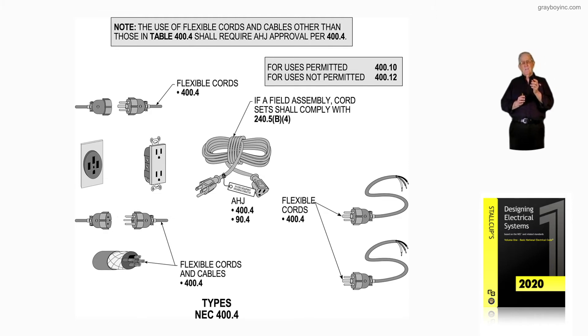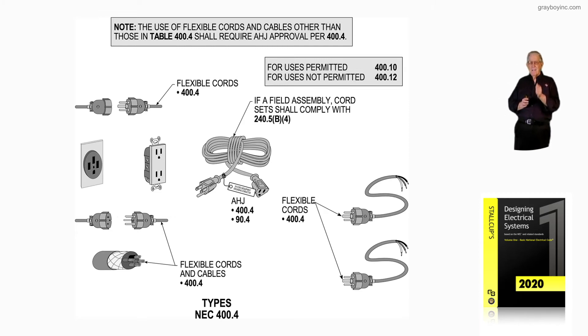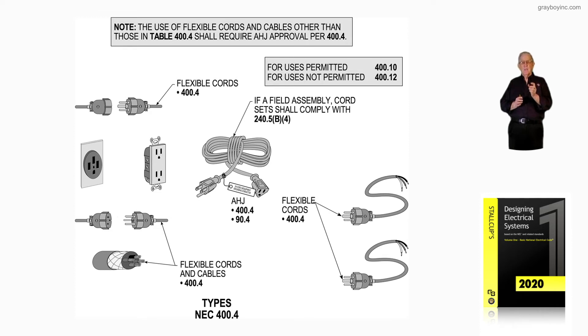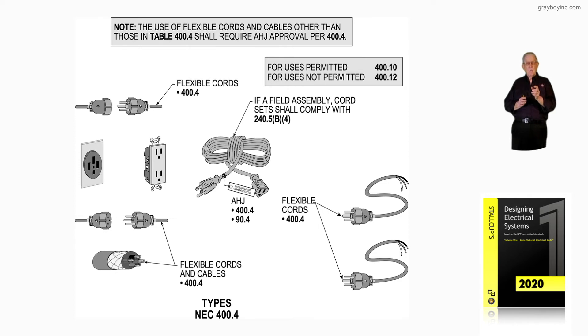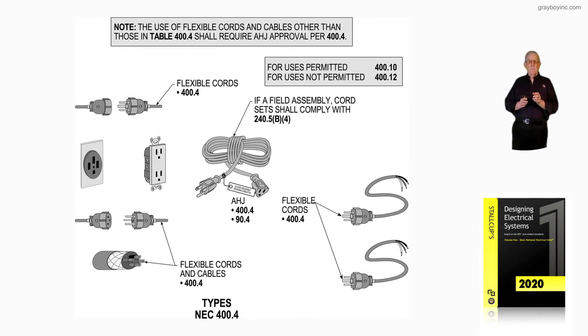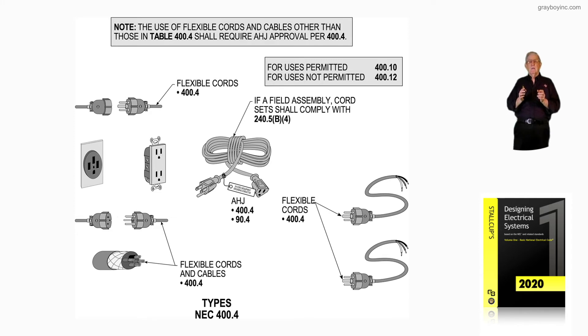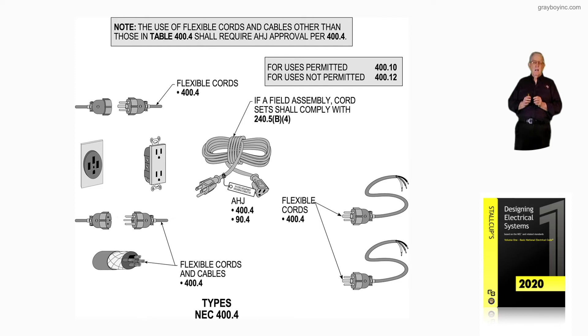And the note says yes, if the type of cable or cord you're using is not in NEC 400.4, the authority having jurisdiction could approve such a cable wiring type method — a flexible cord cable type — that's not listed in NEC 400.4, or if you get with them ahead of time and get their permission on how it's listed from the manufacturer and so forth.